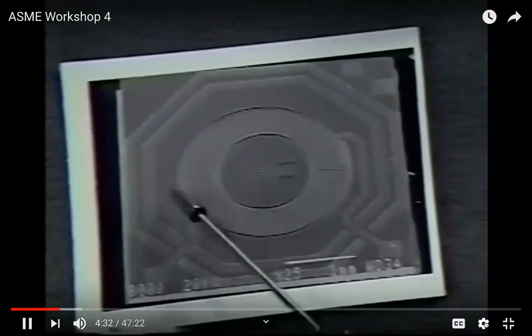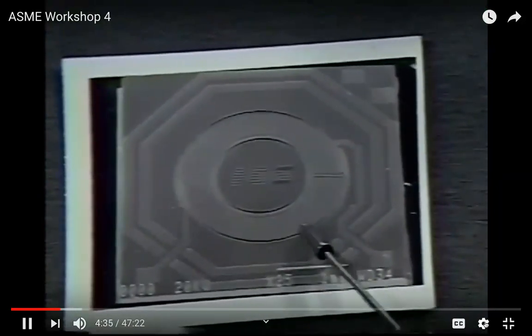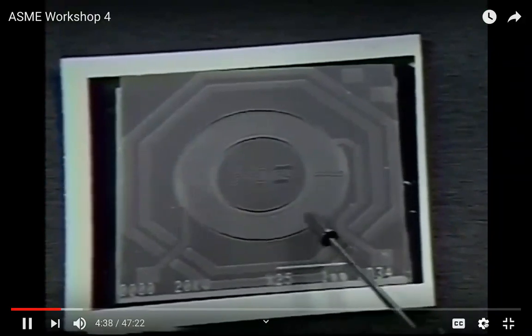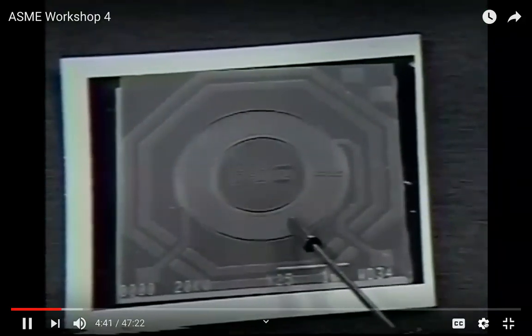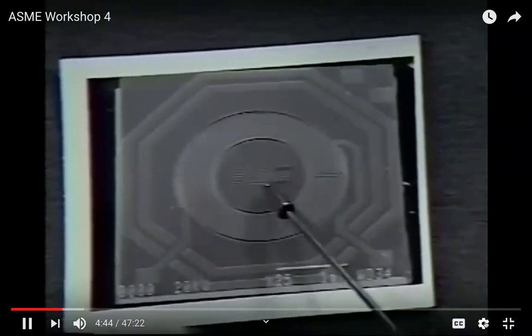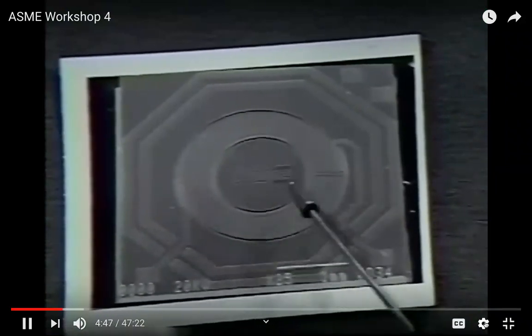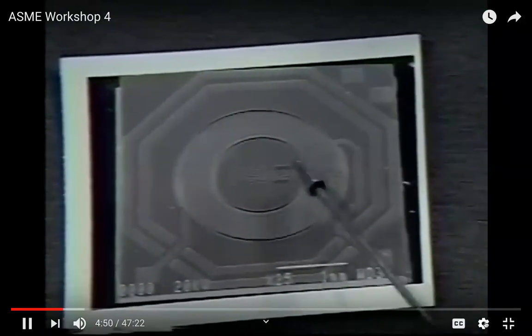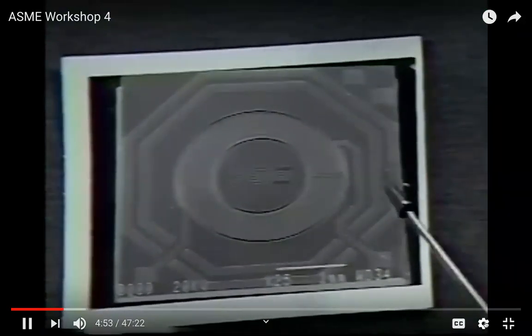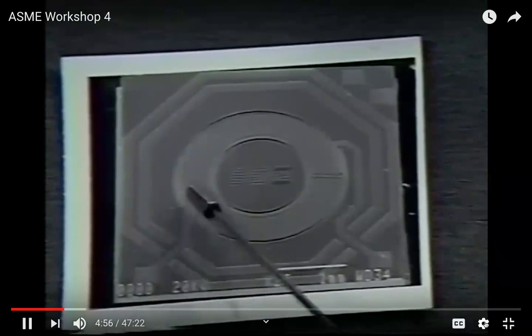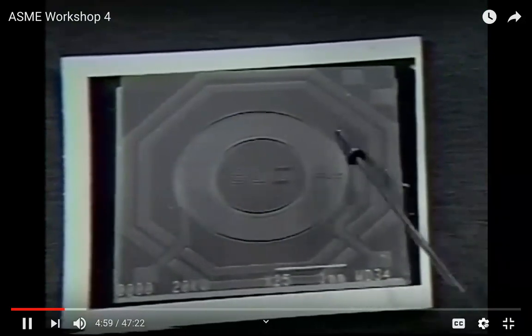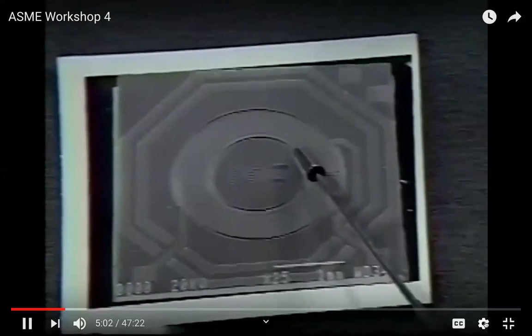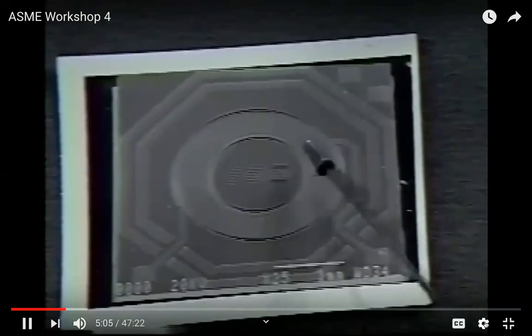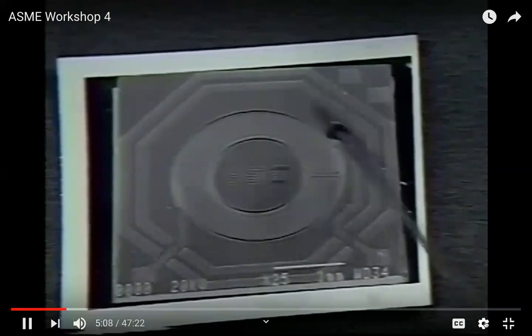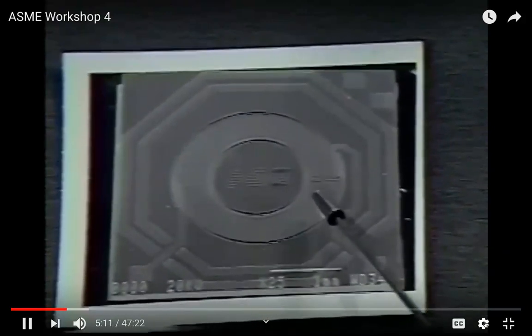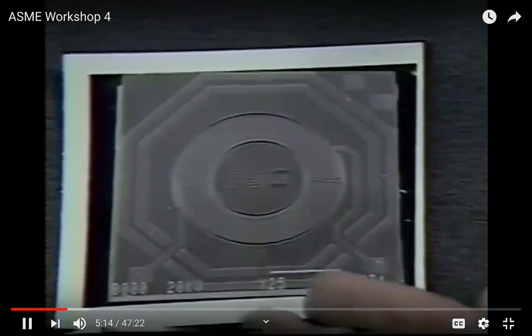This is nominally, well, it's very close to a circular outside hinge. The gray area here is the thick aluminum over the thin silicon diaphragm. In the center is a boss, actually octagonal, but on the top surface we can make an inner hinge, which also provides a thermal isolation function, with a circular mask feature and two electrical connections: one going to a contact around the outside of the part, and the other going to a contact on the inside. As current passes through this device, it goes radially through an implanted area around the entire part, making it very close to circularly symmetric.